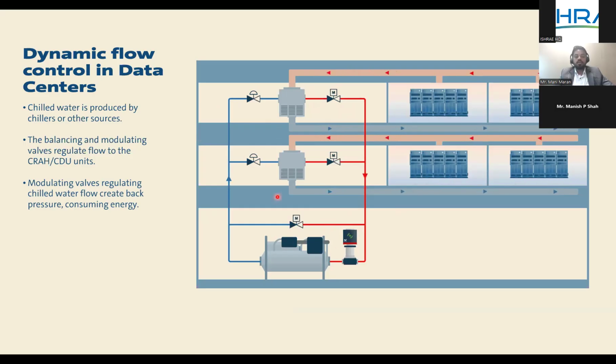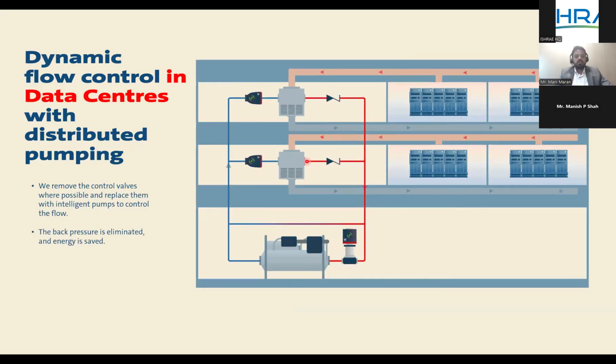This is a challenge that we see, which can be overcome by the way we can decentralize the pump and give a local temperature control to the pump. And on the other hand, if the balancing is not proper, the impact that it brings to the system is much bigger than the pump energy that we are talking about. If there is a low delta T difference between supply and return, the chiller will experience low delta T, and that will pull down the efficiency of the chiller, as well as the efficiency of the plant room, and it increases the PUE. So it is directly linked to the PUE, and we want to address those by changing the concept of how we are doing it today.